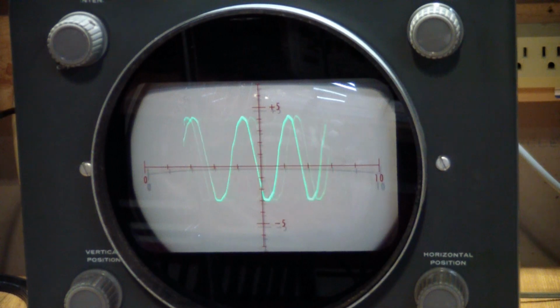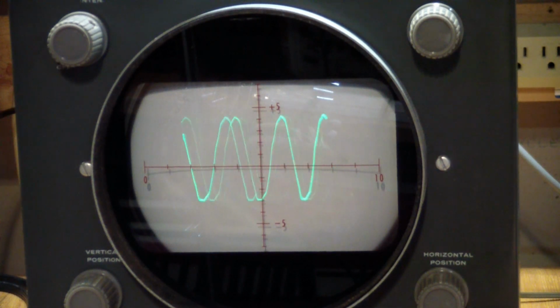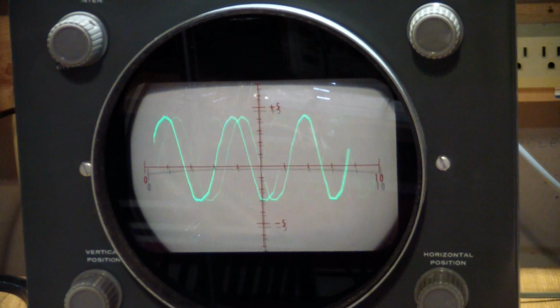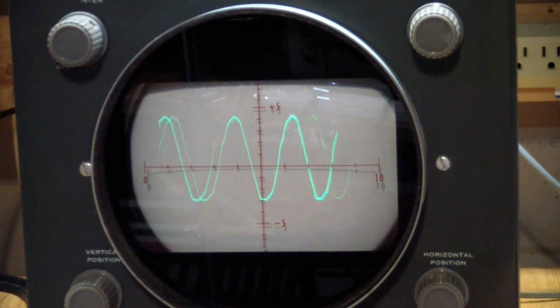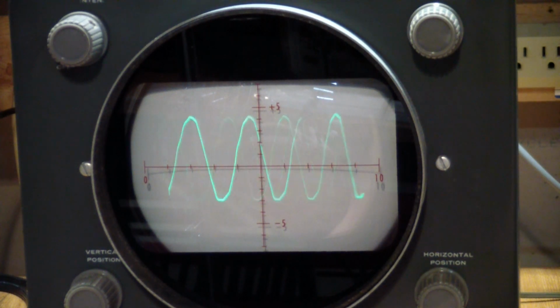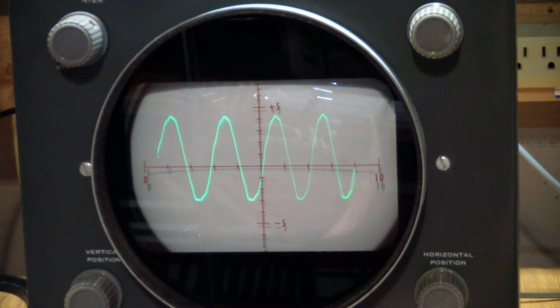and there are our sine waves. Now I'm supposed to adjust this so we can see 4 cycles of the sine wave on screen, and the frequency fine adjust will essentially let me stabilize it. So there you go. We have 4 cycles of a sine wave as generated by the calibration output, and the camera actually reduces the flicker, but you can imagine at 60 Hertz it flickers pretty good.